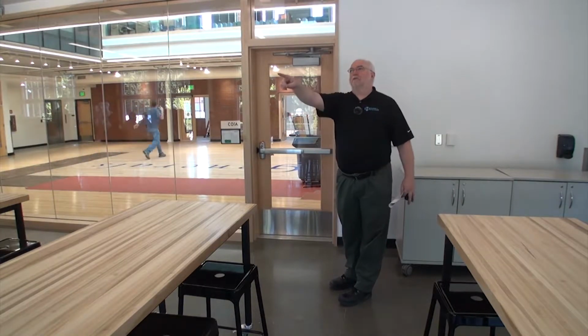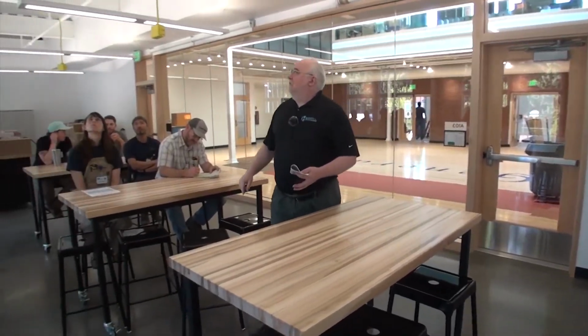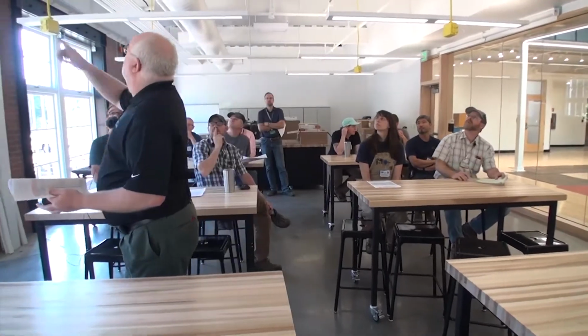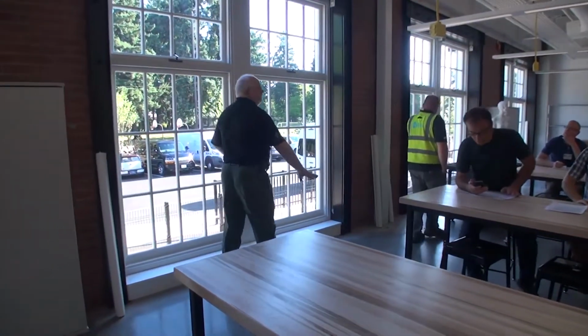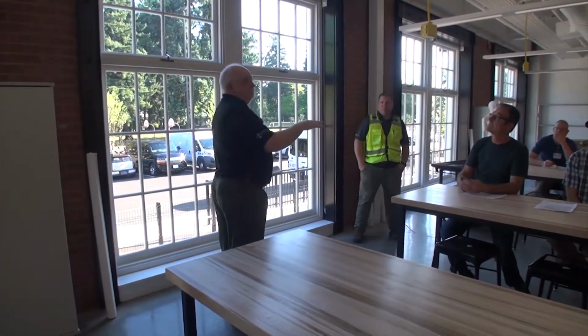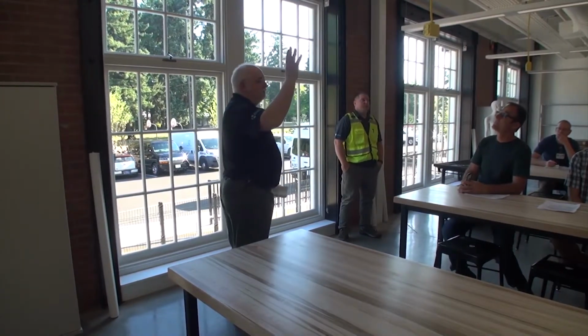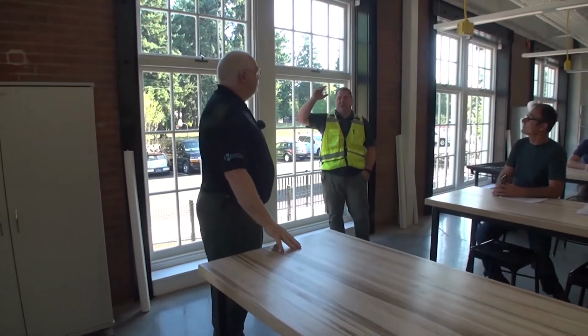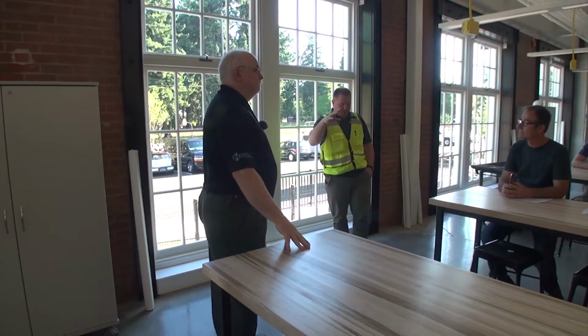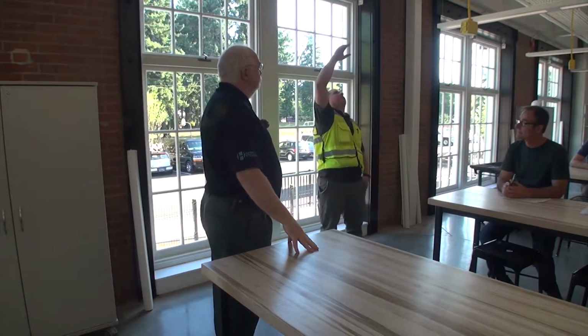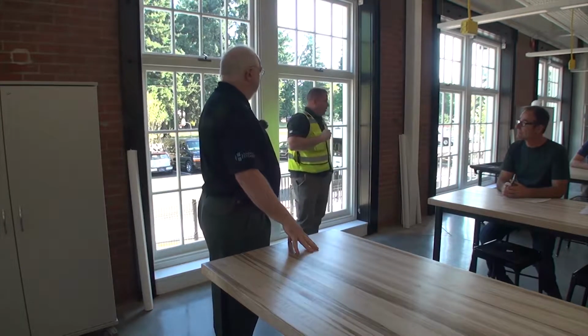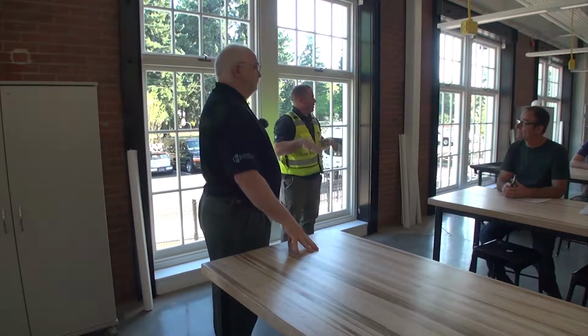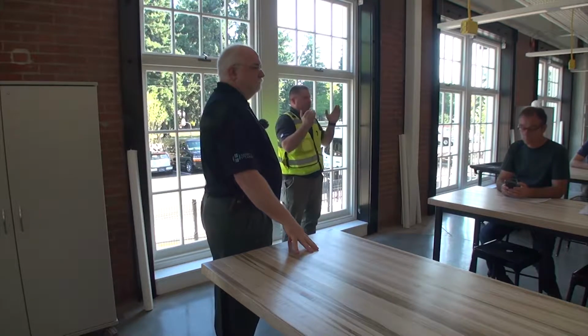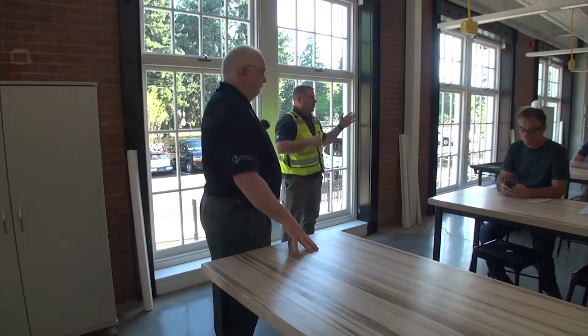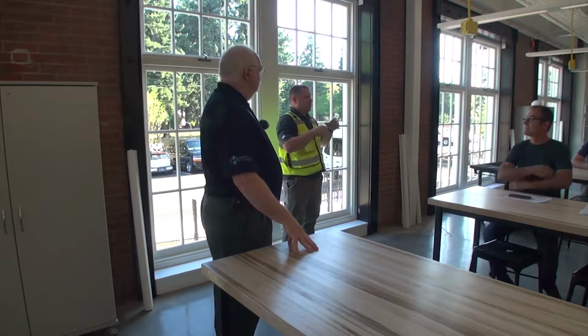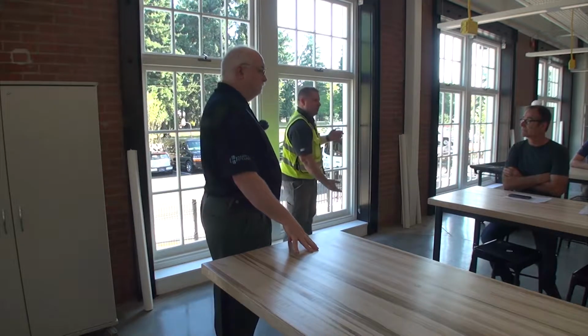The other difference in this room is that we suddenly have the photocells operating here. Those lights aren't dim because they're broken, they're dim because this photocell is detecting the light from the window and adjusting this area since it's bright enough without those being on at full. Specifically, ceiling mount photocells work on the reflective properties of the space - they sense the light that hits the floor and bounces back up to the sensor. Some spaces are more responsive than others, and a lot of that depends on the environment around it. If the ground is very dark, your sensors are going to be more responsive because they're looking for smaller amounts of light since it doesn't reflect much.